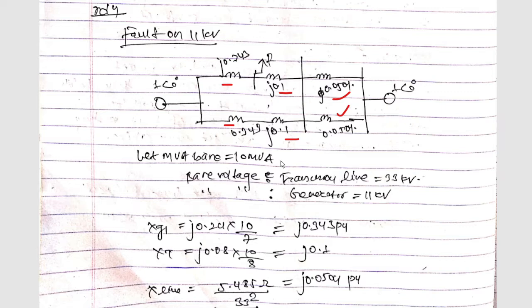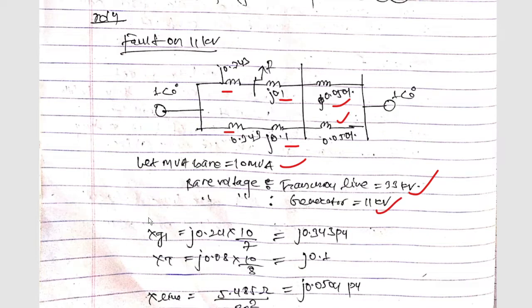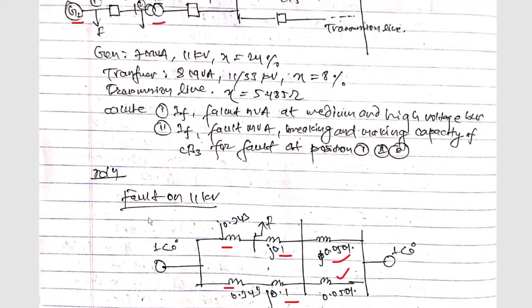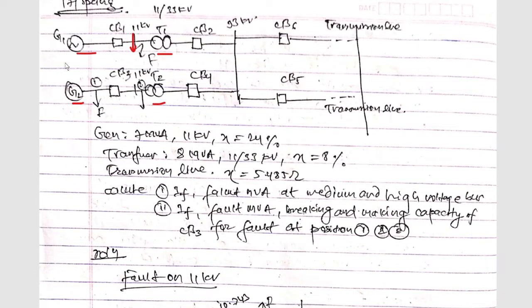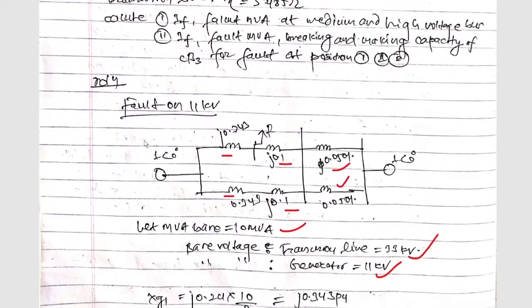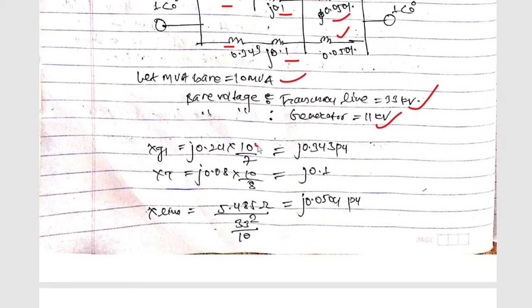In order to calculate these parameters, let's assume a base of 10 MVA. The base voltage at the transmission line will be 33 kV, and the base voltage at the generator side will be 11 kV. Now xg1 is calculated as: the old x value is 24%, so 0.24, multiplied by (new MVA / old MVA) = 10/7. This gives xg1 = 0.343 per unit.